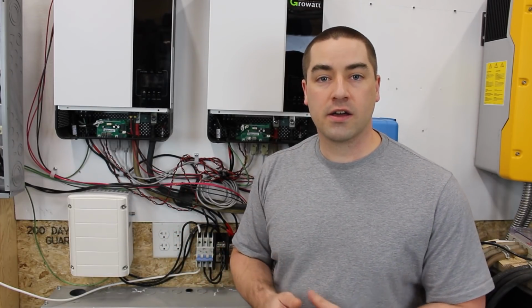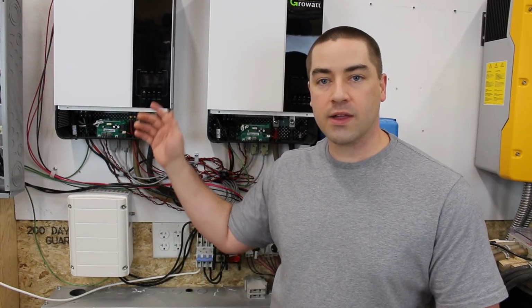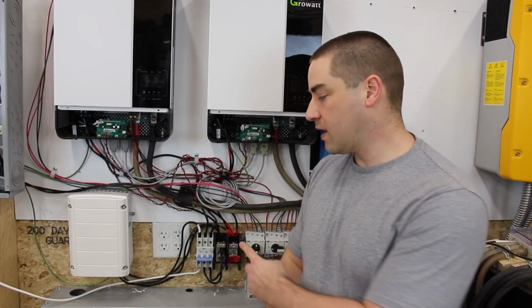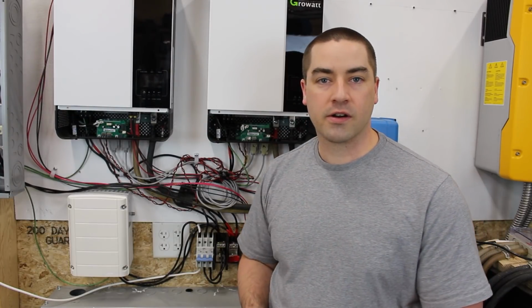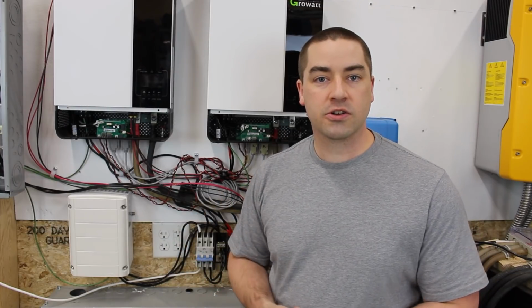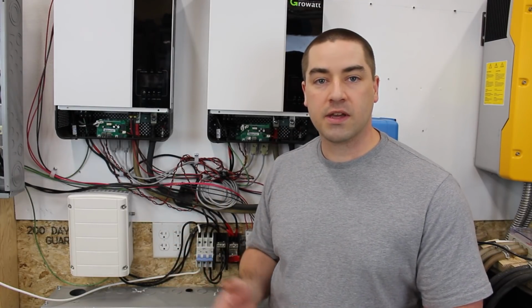Now let's say you have one auto transformer and 3 inverters. They do make a 4-pole circuit breaker. So these are MCB or miniature circuit breakers, and you can get them in a 4-pole design as well.